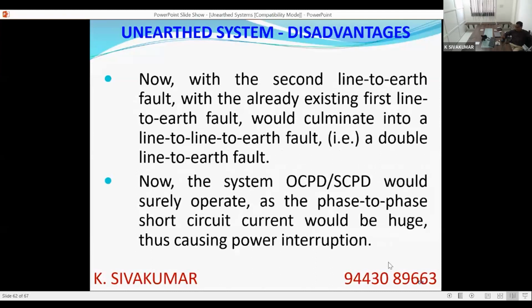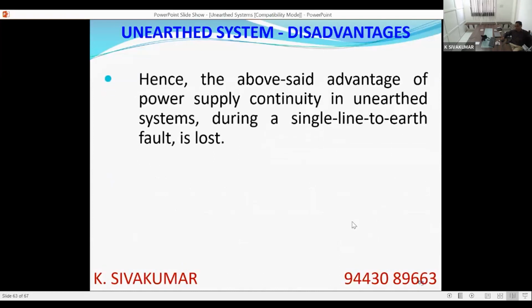Now, the system OCPD may not detect a single phase to ground fault, as the current is negligible. But when this becomes a line to line short circuit, definitely the currents are huge. So definitely the system OCPD or SCPD, overcurrent protective device or short circuit protective device, will operate, as the phase to phase short circuit current is very high, even in kiloamperes. So definitely there will be a power interruption. So whatever we told earlier for initial understanding, that the advantage of an ungrounded system is no interruption, the advantage is lost. Because a single line to ground fault will never remain a single line to ground fault, it will soon culminate into a second line to earth fault, ending up in a line to line to ground fault.